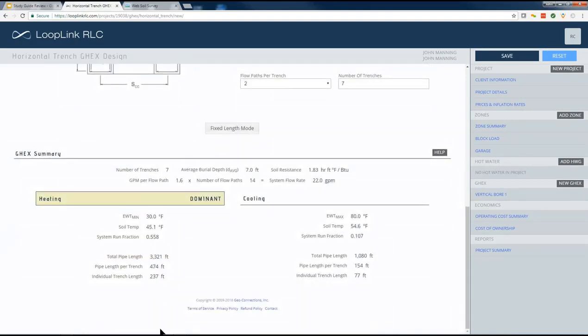So we're ending up with about 250-foot long trenches, and we just buy a 510-foot 3/4-inch U-bend and put it in the bottom there, and you've got extra feet on the end of the pigtails. But obviously, when you do something like this, it takes a much bigger piece of land. But notice how much less pipe length I have with that configuration, individual pipe length per trench. We might get away with a more reasonable pumping solution with these shorter loop lengths than the slinky I showed before.